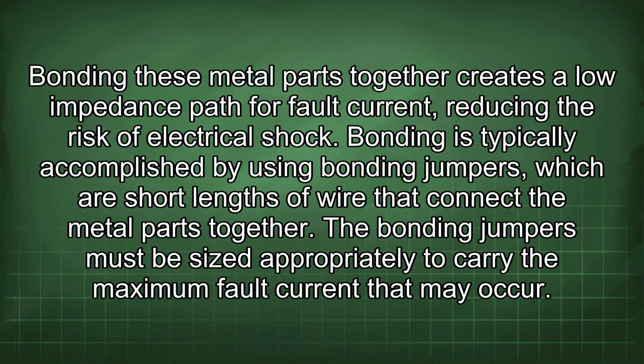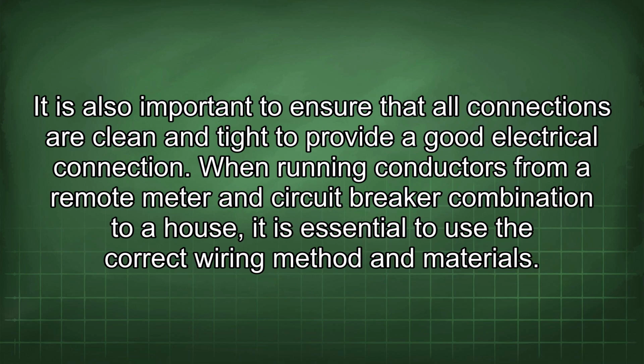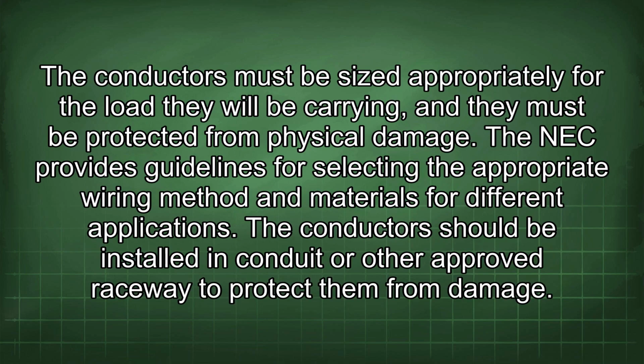Bonding is typically accomplished by using bonding jumpers, which are short lengths of wire that connect the metal parts together. The bonding jumpers must be sized appropriately to carry the maximum fault current that may occur. It is also important to ensure that all connections are clean and tight to provide a good electrical connection. When running conductors from a remote meter and circuit breaker combination to a house, it is essential to use the correct wiring method and materials. The conductors must be sized appropriately for the load they will be carrying, and they must be protected from physical damage. The NEC provides guidelines for selecting the appropriate wiring method and materials for different applications.